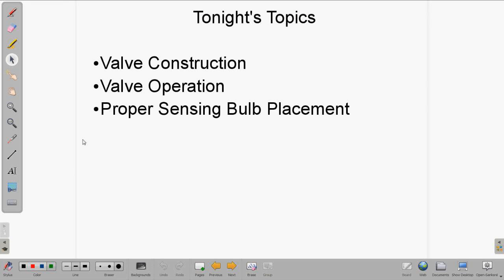Okay, so tonight's topics, we're going to cover the valve construction for the TXV, how the valve operates, and how to properly place the sensing bulb when you're replacing a TXV, and also when you're troubleshooting one to make sure it's mounted correctly.